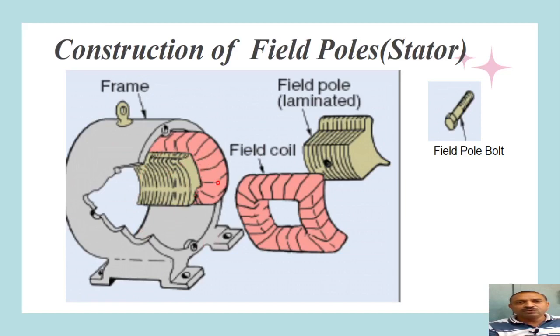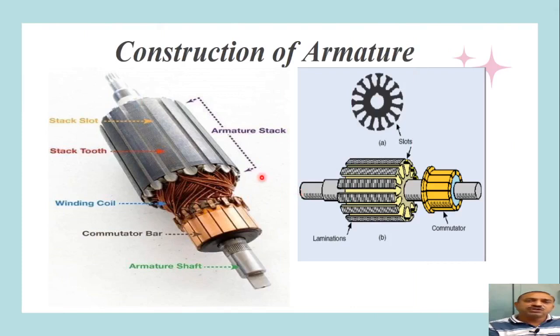Now let us see the construction of the rotating part, which we call the armature. At its center, the armature has a shaft supported at both ends by bearings for smooth rotation and to reduce friction losses. The armature stack houses coils forming the windings. The armature coil terminals are connected to the commutator, which consists of a number of copper bars or strips. Each strip is insulated from the nearby strips.